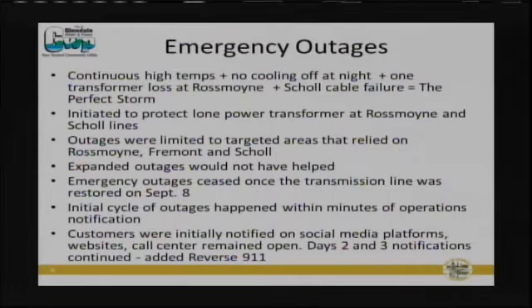The initial cycle of outages happened within minutes of operations notification. When we got that emergency alarm, we initiated outages immediately. There's been talk about why there wasn't more notification or a longer lead time, but we didn't want to call an outage we didn't think was going to happen. In this case, once the alarm went off because of the failed cable, we began emergency operations to bring down the amperage on the transformer and cool it so we would not cause further damage.